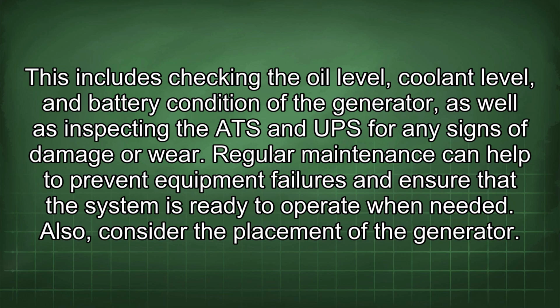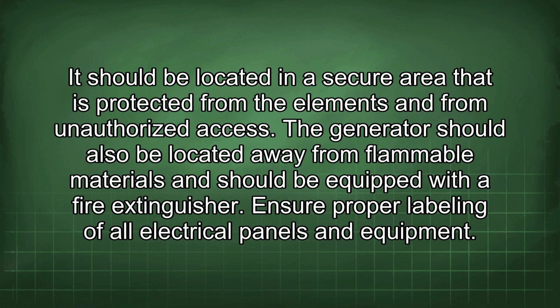Also, consider the placement of the generator. It should be located in a secure area that is protected from the elements and from unauthorized access. The generator should also be located away from flammable materials and should be equipped with a fire extinguisher.